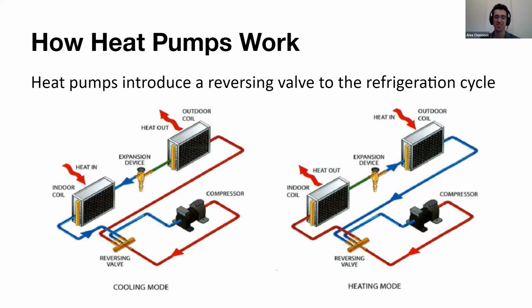So how do you actually reverse the cycle? You don't just flow the other way. It always goes out of the compressor in the same direction, but you have a device called the reversing valve. In the summer, you can send discharge gas out of the compressor to the condenser outdoors, and that really hot gas can get cooled by the warmish air outdoors. In the wintertime, you send the discharge gas right to the indoor units, which become the condenser coils.